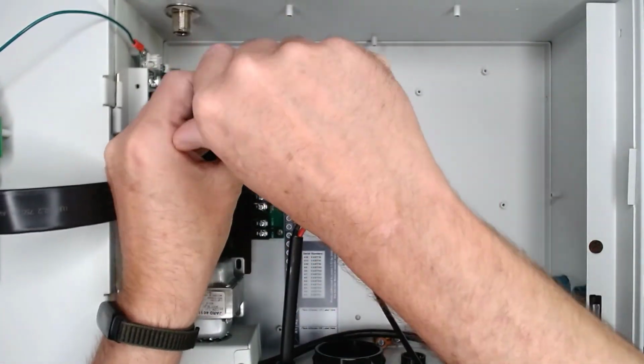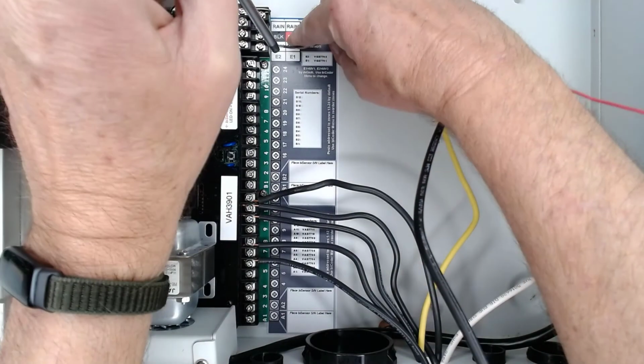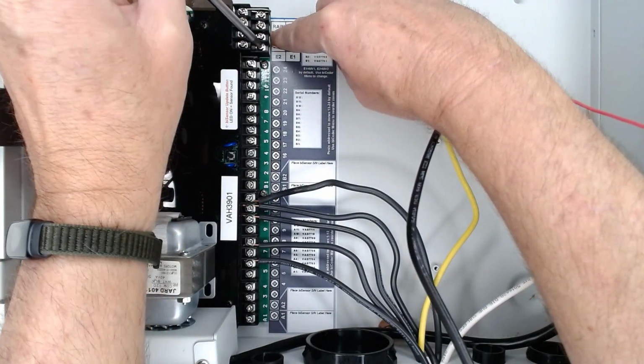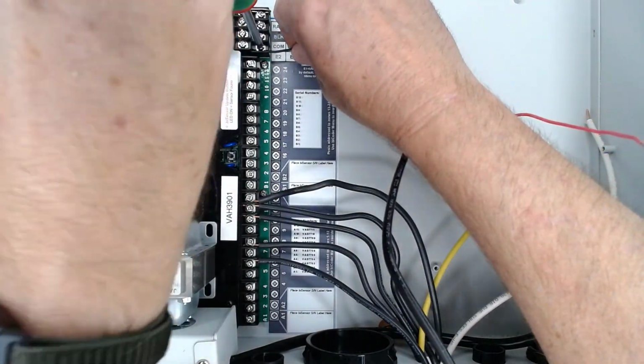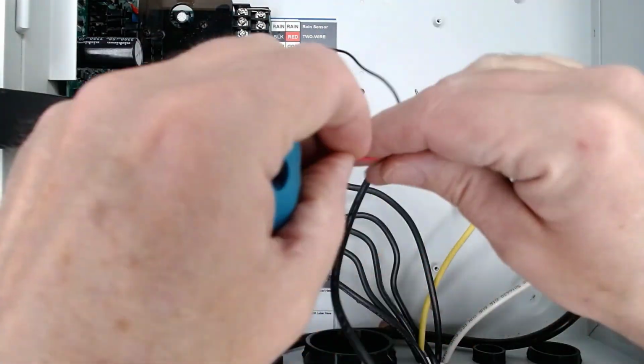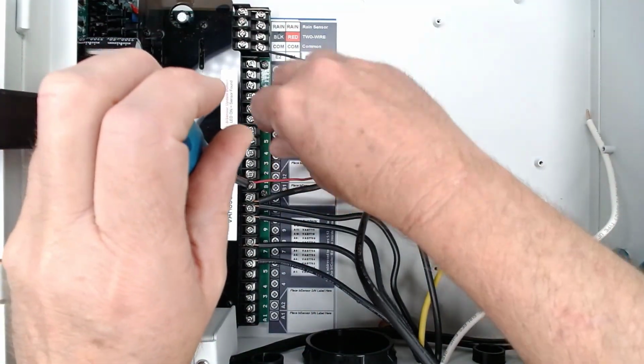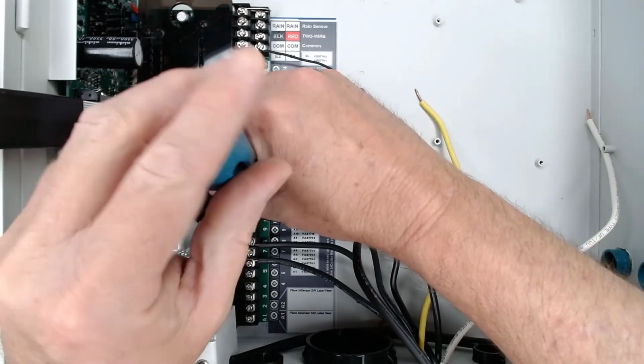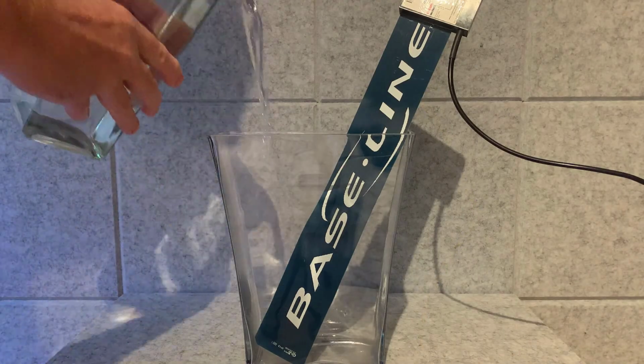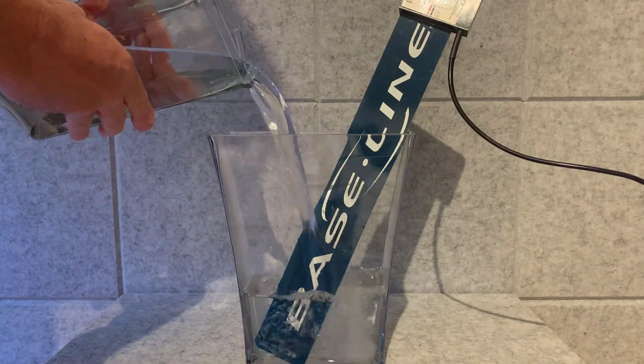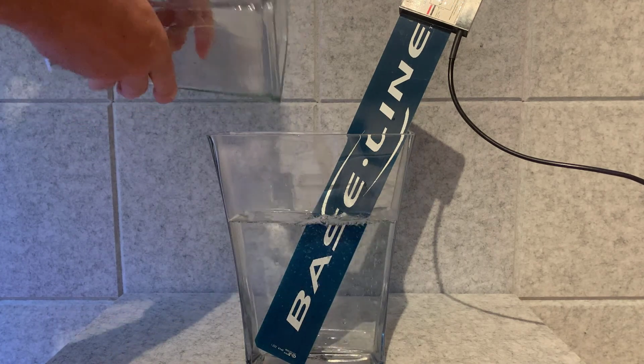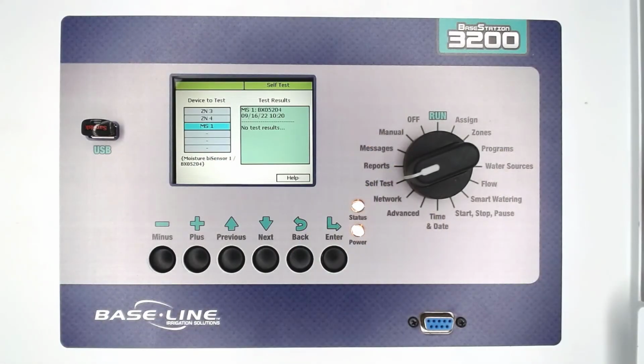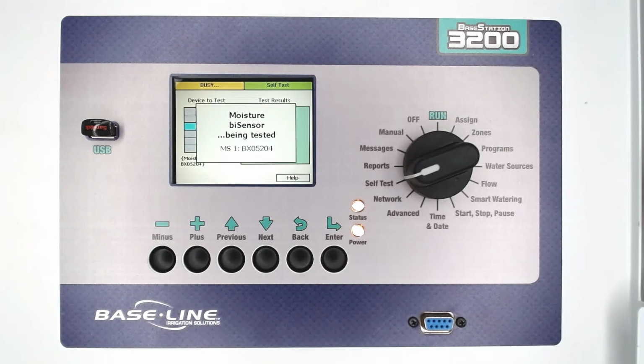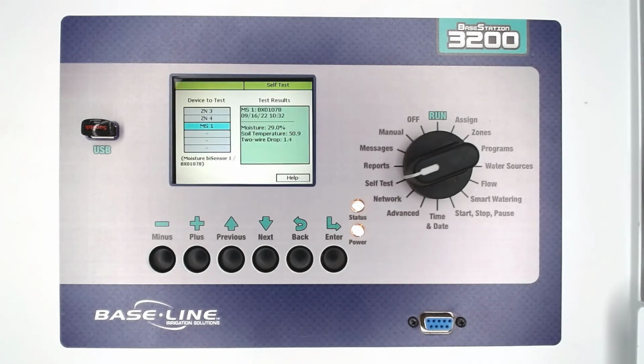If you're working on a conventional wired system, you can connect the black sensor wire to the common and the red sensor wire to terminals A1, A2, B1, or B2. Those are the only conventional wire terminals that look for a moisture sensor. We'll want to wet the moisture sensor before testing it, so find a bucket and fill it up. Power the controller back up and return to Test Single 2-Wire Device, rerunning the test on Moisture Sensor 1.